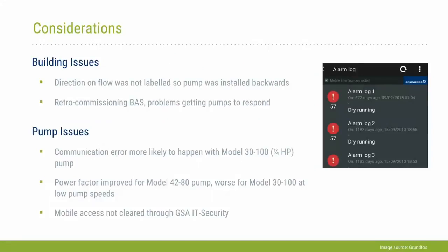So here are some issues we ran into during this project that are good to consider in the future. For the air handler applications, the flow direction on the pipes wasn't labeled, so when the O&M staff initially went in and installed one of the pumps, they installed the pump backwards. We had to go back and rectify that and make sure it was flowing correctly. The other piece that Jesse mentioned was the retro commissioning. We had a number of points that were either programmed incorrectly in our BAS or bad sequences in place, which led to incorrect operation of the system. Once we had those fixed and the entire BAS was reprogrammed, we were seeing the appropriate response from the air handlers and the circulator pumps.